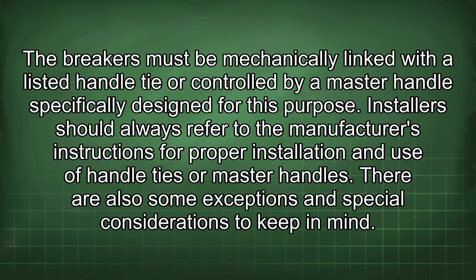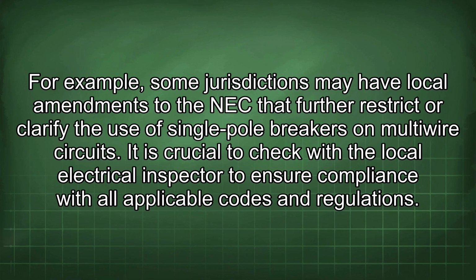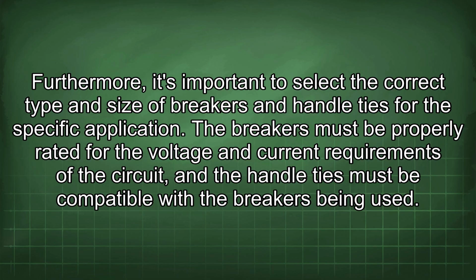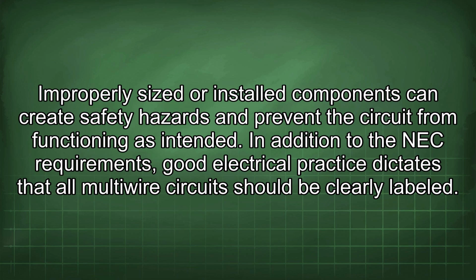There are also some exceptions and special considerations to keep in mind. For example, some jurisdictions may have local amendments to the NEC that further restrict or clarify the use of single-pole breakers on multi-wire circuits. It is crucial to check with the local electrical inspector to ensure compliance with all applicable codes and regulations. Furthermore, it's important to select the correct type and size of breakers and handle ties for the specific application. The breakers must be properly rated for the voltage and current requirements of the circuit, and the handle ties must be compatible with the breakers being used. Improperly sized or installed components can create safety hazards and prevent the circuit from functioning as intended.